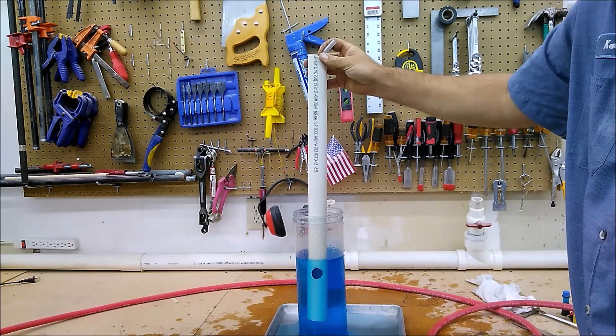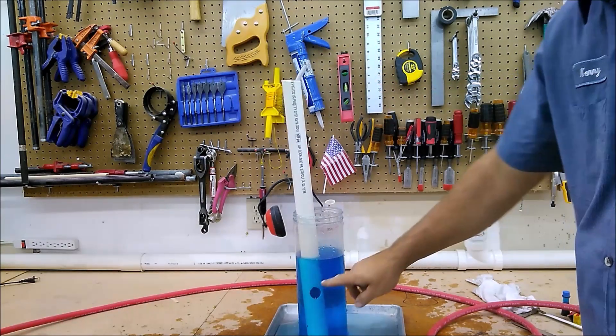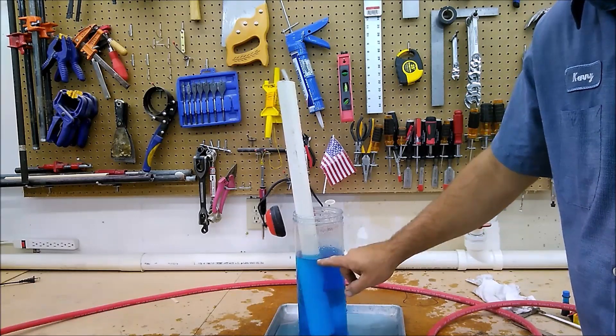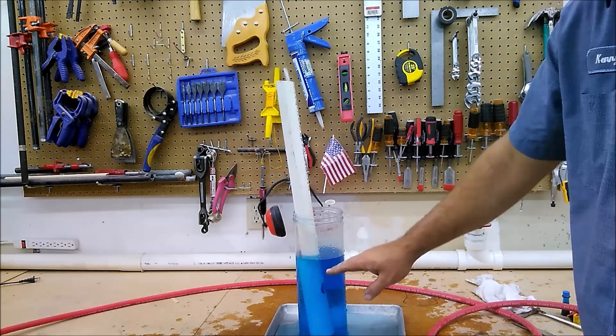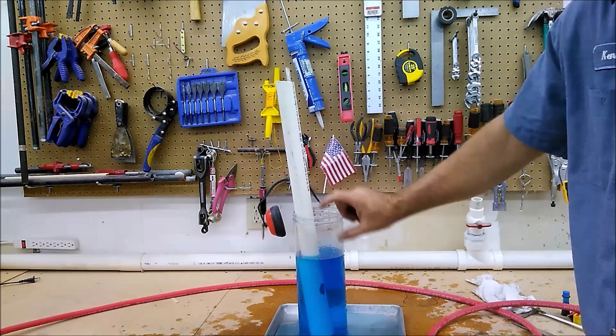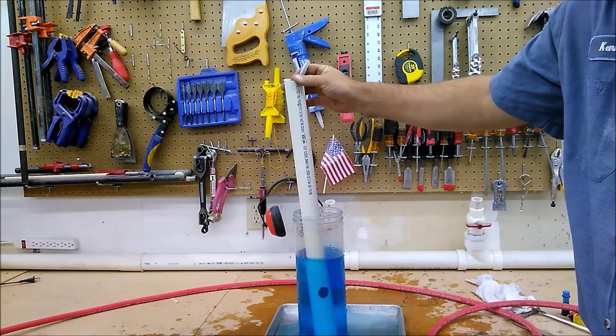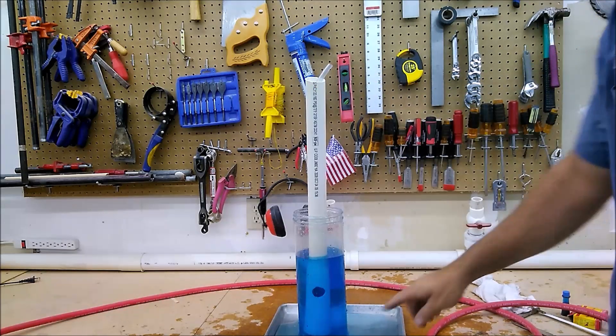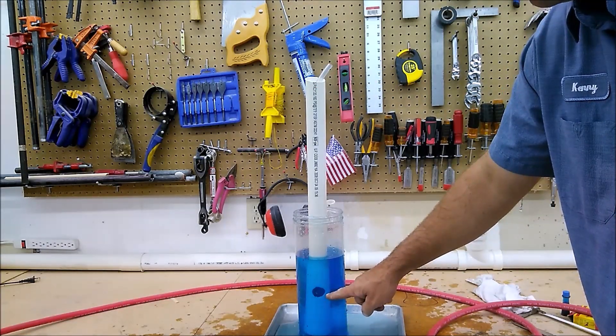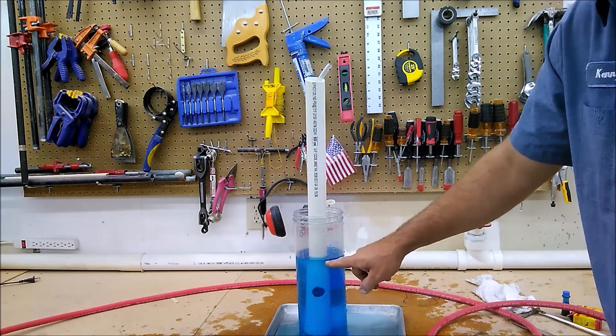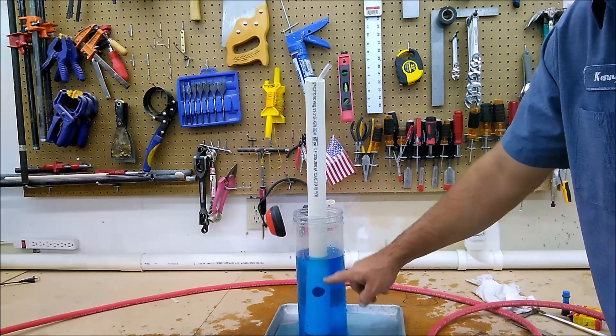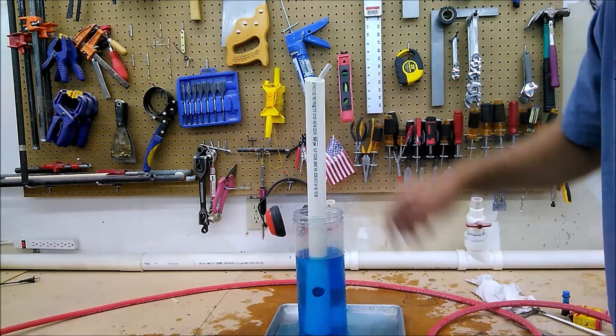It makes a little bit less sense, but even if you're under water here, you've only got 25% submergence here and a whole bunch of room for the water to stack up here. So you're going to be moving water up to here, but then when it gets to this hole, you're not going to have very much additional head left over to push it on up the pipe.